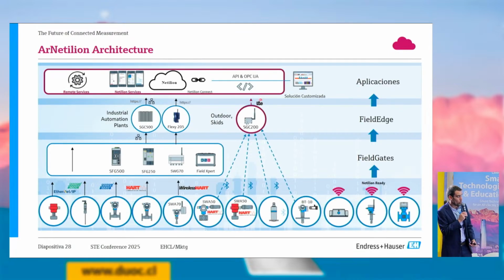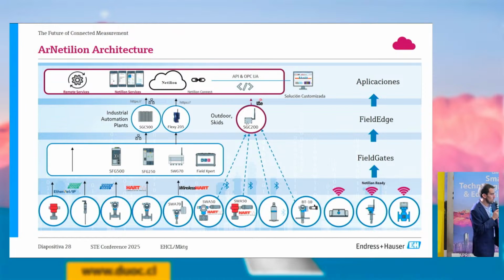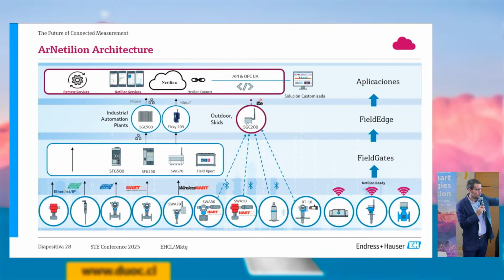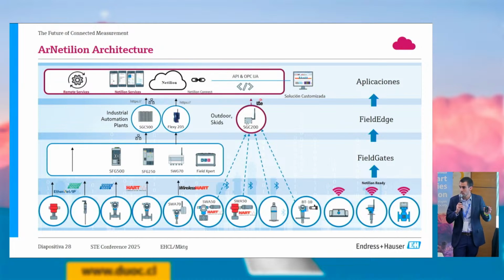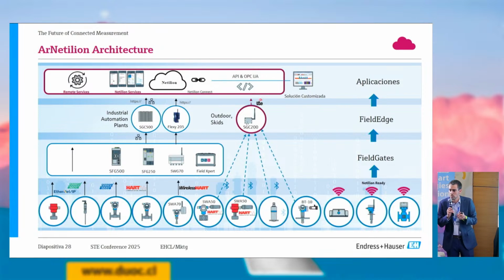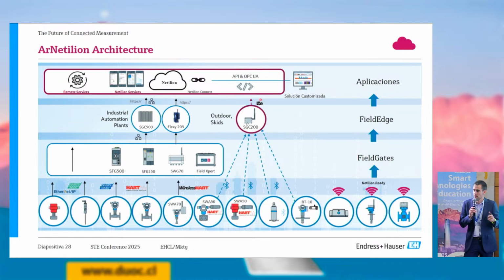The current way we can take measurements into Netilion can be from Ethernet IP, Profibus, HART, even wireless HART. Even devices that are not from Endress+Hauser can be on Health or on Library. As I said, NAMUR NE107 is an open structure, an open protocol, so third-party devices will also be visible there, showing that a radar of another brand is under failure, or a liquid analysis device of another brand is having an issue.